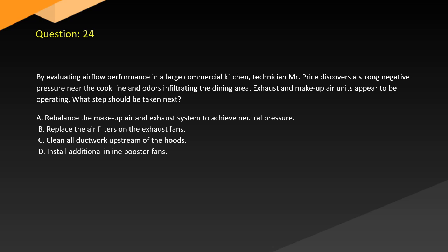Question 24. By evaluating airflow performance in a large commercial kitchen, technician Price discovers a strong negative pressure near the cook line and odors infiltrating the dining area. Exhaust and makeup air units appear to be operating. What steps should be taken next? A. Rebalance the makeup air and exhaust system to achieve neutral pressure. B. Replace the air filters on the exhaust fans. C. Clean all ductwork upstream of the hoods. D. Install additional inline booster fans.